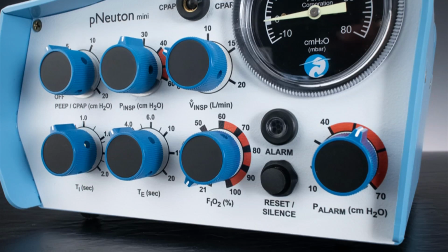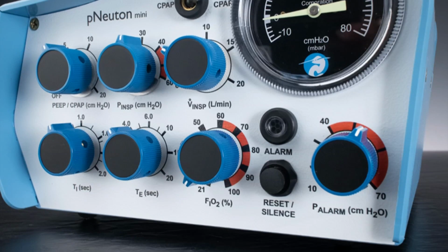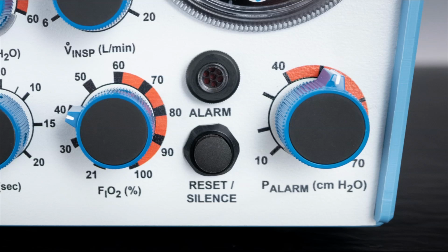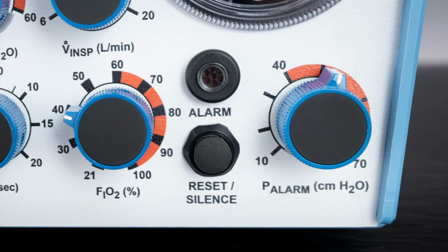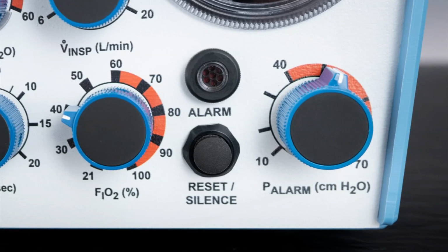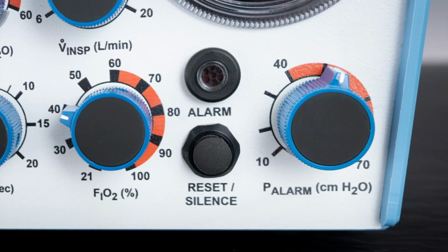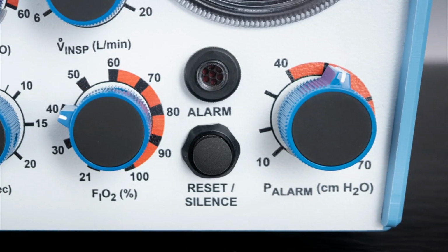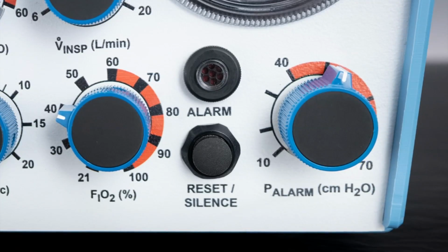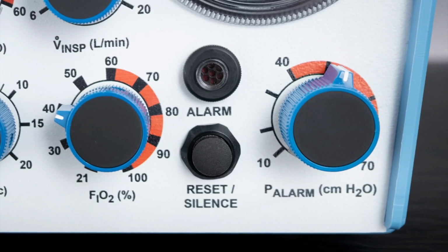The ventilator automatically monitors patient pressure at all times. An advantage of the pNeuton Mini's alarm system is that if there's ever a ventilator alarm, for whatever reason, a disconnection in the patient circuit, a crimp in a patient circuit tube, or circuit pressure drops to less than 3 centimeters of water, the audible alarm will sound within 10 seconds, and the visual alarm indicator will illuminate.